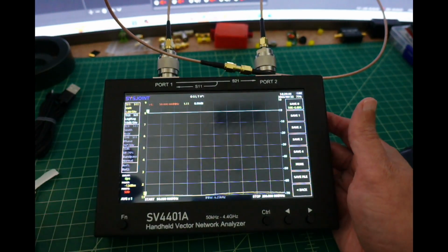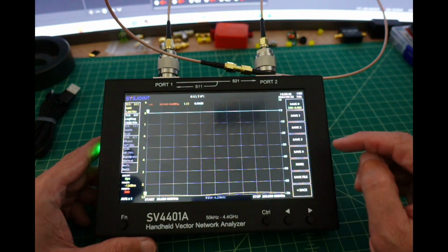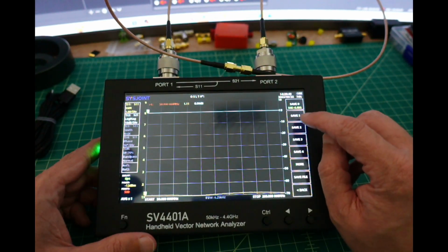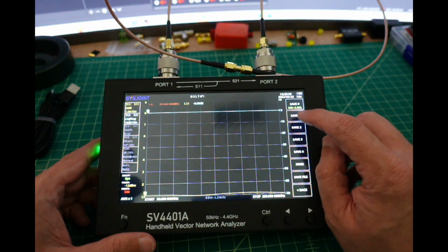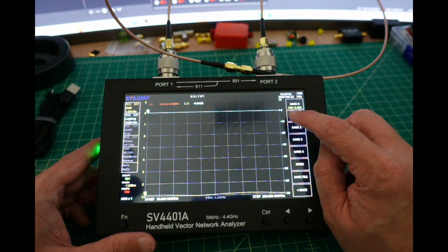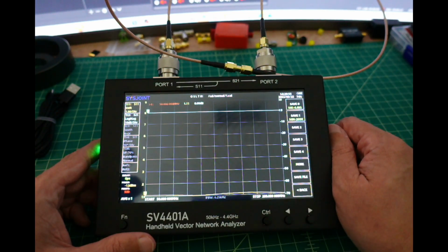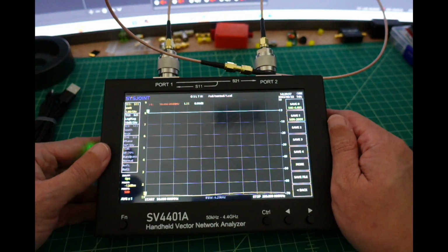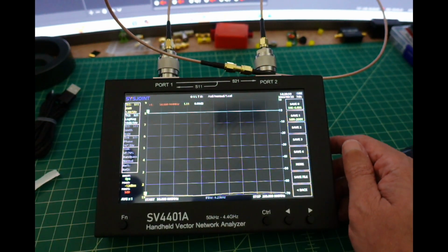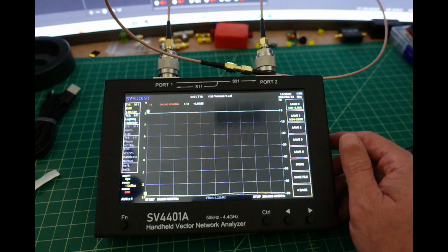And now it's calculating our calibration data, and it's asking us to save this. Here I can see that number 1 is blank. There's nothing in slot 1. So I'm just going to go ahead and save it right there. And there we go. That calibration is loaded into our device memory. Now what we want to do is measure a filter. So let me go ahead and get that ready.